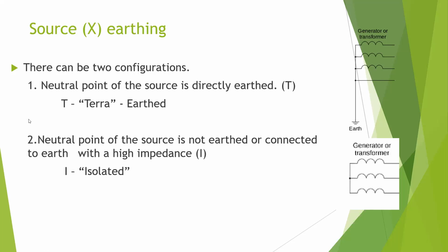So you should know now that the source earthing can be done in two ways. The first one is connecting the source neutral to earth, and the second is not connecting the source neutral to earth, or connecting it to earth through a high impedance. So this is directly connecting the source neutral to earth, and in this diagram the source is isolated. That means it is not connected to earth. So these are the two standard configurations of earthing defined for the source side.